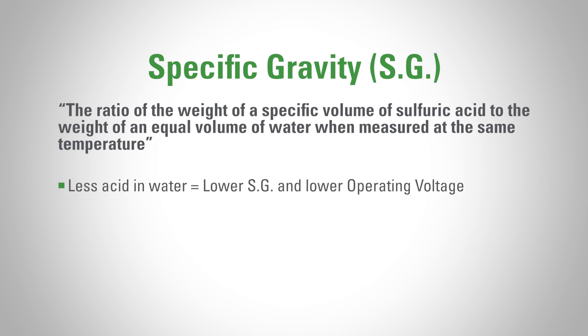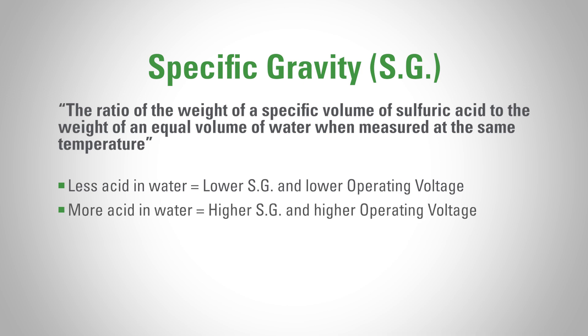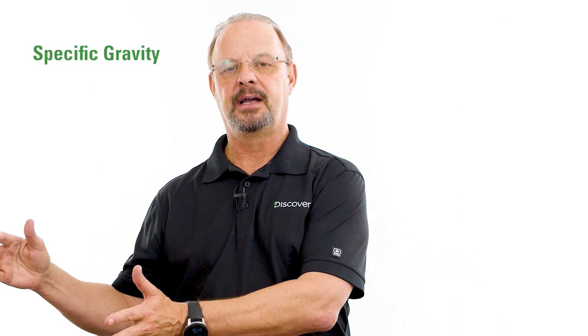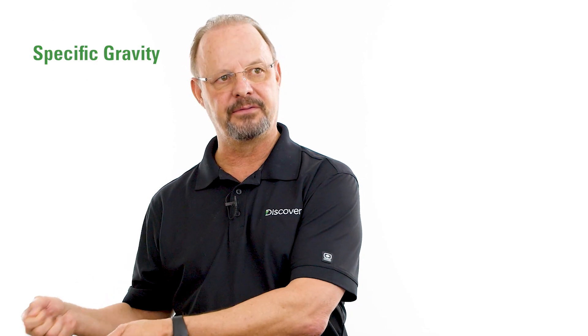Less acid in water equals lower specific gravity, and ultimately that translates into lower operating voltage. More acid in water equals higher specific gravity and higher operating voltage. For all you battery guys out there who used to test batteries with a hydrometer, a lower reading on the hydrometer would equate to a lower voltage reading on the battery with a voltmeter.